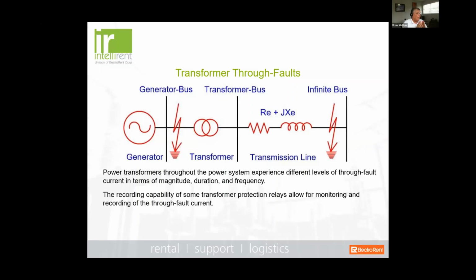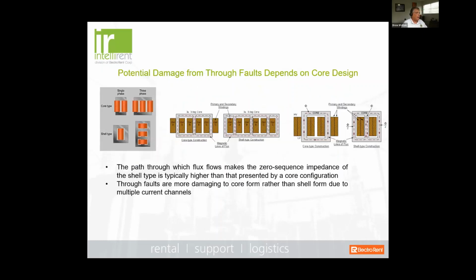So the recording capability of your transformer protective relays actually will allow for monitoring and recording through fault current and through fault activity. Now, in having this discussion with some protection engineers, I was talking to one gentleman that's been around Schweitzer Engineering Labs for many, many years. And he said, Drew, yes, our transformer differentials do have through fault monitor, as do most other modern transformer differential relays. However, in my experience, people don't want to set them, or there has been a neglect in setting up the through fault monitor in the industry. And he agreed with me that this is an important step in terms of your protective relay.